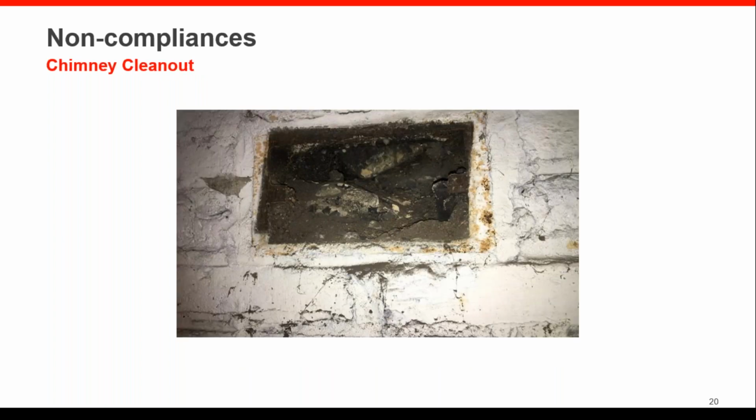This is another example of clearly where we've got some chimney issues here. And you can see that the whole base of that chimney is full of debris. And so in those kinds of situations, pull out your mirror and take a look, or pull the vent connector up a little higher up the chimney and have a look up there and see what that situation is. And if you've got situations where you get some deterioration, then point that out to the customer, and probably in all cases, you're going to need to tag it.